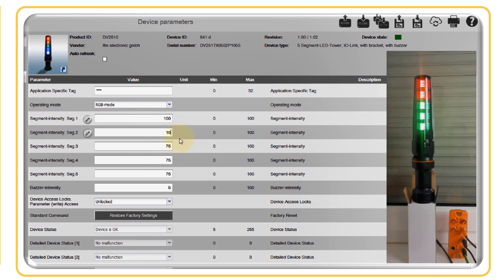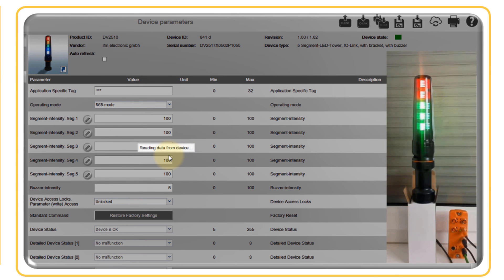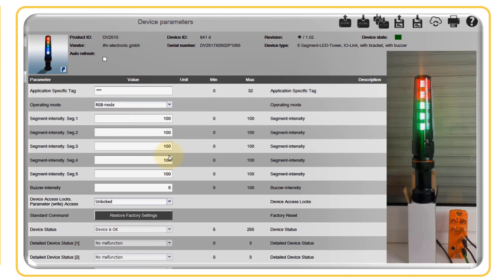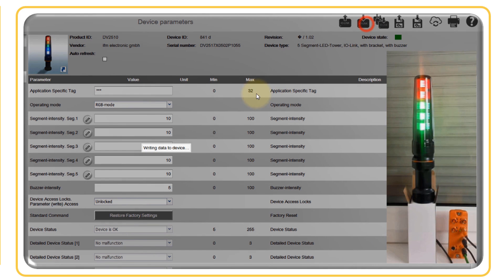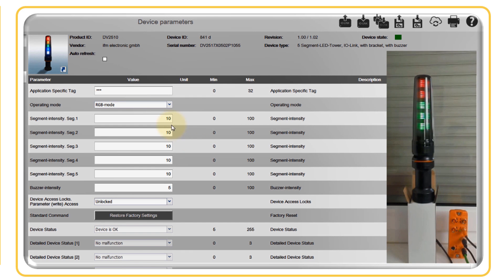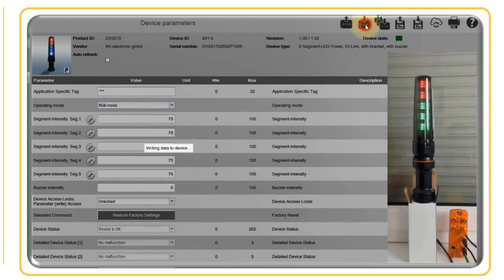The default intensity is 75 percent, the minimum is 0 percent, and the maximum is 100 percent. After changing to 100 and writing to the device, the intensity changes within fractions of a second while the signal light is still operating — no need to stop it. If the lamp is in a dark environment, you can set it as low as 10 percent. This is the flexible way to change intensity from 0 to 100 based on environment conditions.